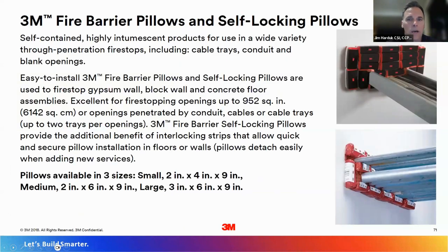The next product I want to talk about, the Firestop pillows. The pillows are a highly intumescent wafer that is sandwiched between mineral wool. So there's multiple layers of this intumescent wafer material and this mineral wool, and they are self-contained in a plastic wrap. It's available in 2 forms. Basically, we have it with Velcro on it, so you can interlock the components together, and we have it without the Velcro strips. We have 3 sizes for the pillows. There's a small, medium, and large. And again, these can be used where you have situations where you have multiple penetrating items, or if you have cable and conduit or cable trays. They are reusable and there's no expiration date on these products. So you can store them for quite some time before they're actually put into use. Next slide.